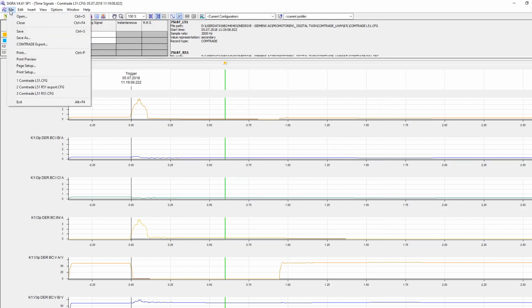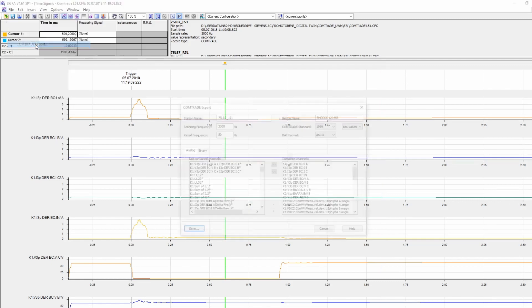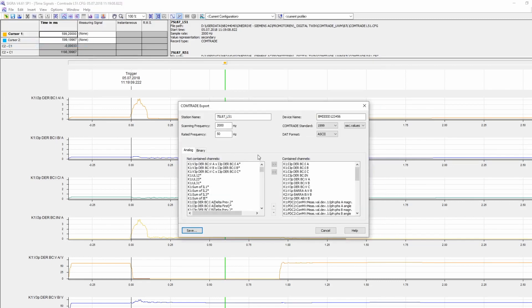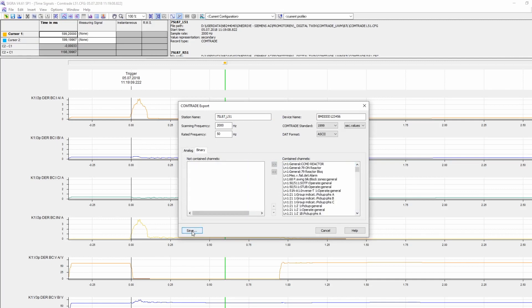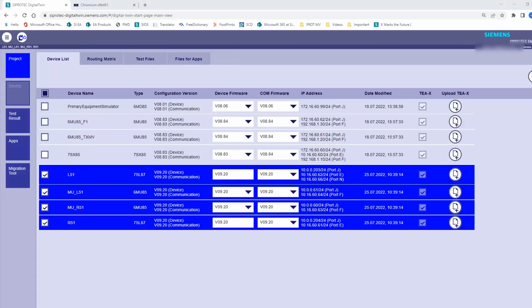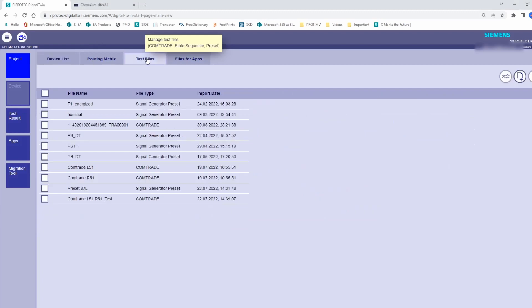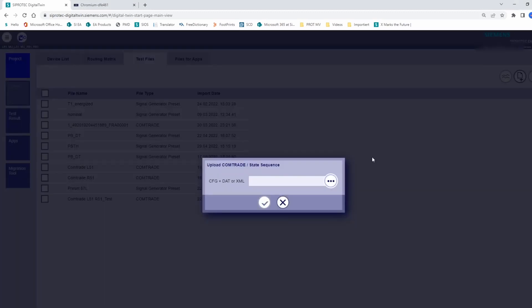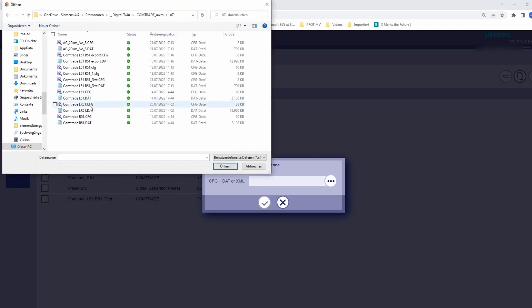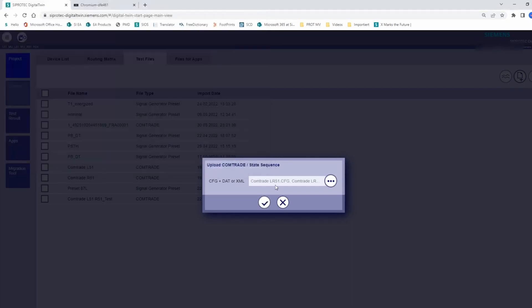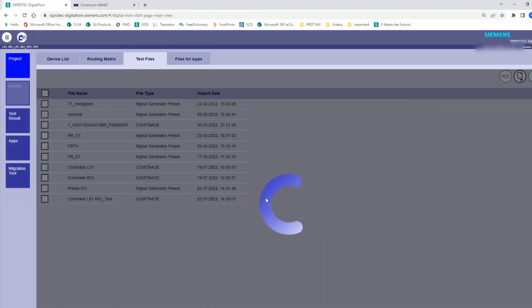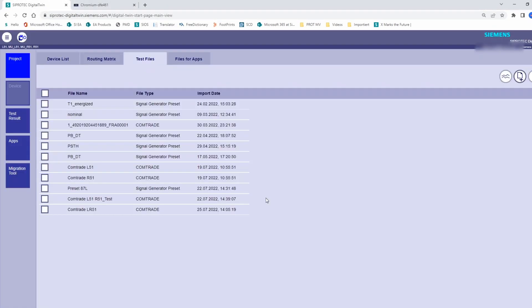First click on File and then Export COMTRADE. The next step is putting this COMTRADE available in Digital Twin. For that you log on in the tool, click on Project, Test Files and select the icon with the plus symbol. Select the files, you will need the CFG and DAT files and upload them. So, once we have it here, then we go to assign the information that we have in the COMTRADE to the devices that we want to simulate.